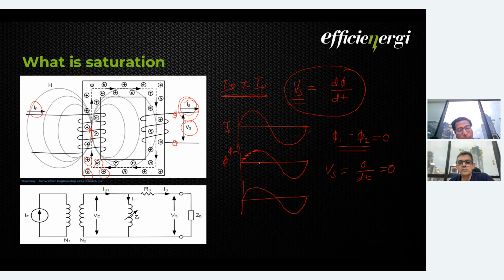So this is where the saturation brings trouble for a relay to understand the exact primary current. So what happens? Just to understand further, we have some burdens connected. Burdens means relay connected. Initially there is no current, so there are no flux lines. As the primary current goes on increasing, there are flux lines associated with the secondary winding, and then based on the burden level, the voltage is induced and the current passes through the relay. This occurs till the saturation point. Till the saturation point, Is is exactly the replica of the primary current.